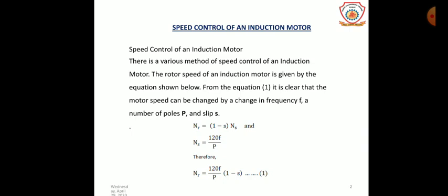As we know, the rotor speed Nr equals (1 - s) × Ns, where Ns is synchronous speed, and Ns = 120f / P. Therefore, Nr = (120f / P) × (1 - s). From this equation, it is clear that the motor speed can be changed by a change in frequency f, number of poles P, and the slip s.